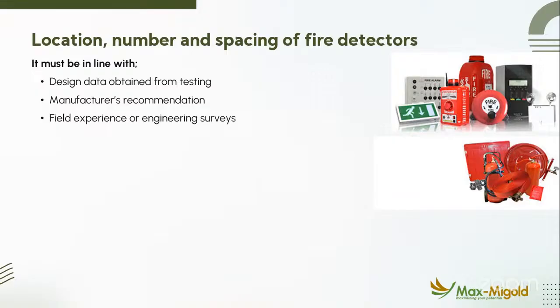So the area to be protected, like I said, the volume of the space will be protected. So length times breadth times height matters in fire. The volume of the space matters. So for fire detectors, it is more of the length and the width of the space. That helps us to know how to position the smoke detectors and what quantity of smoke detectors we should install. All right. So the recommendation is actually based on the size of a building and based on NFPA standard, also the obstructions in that space will be taken care of.